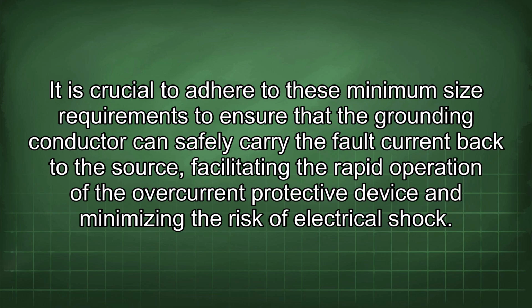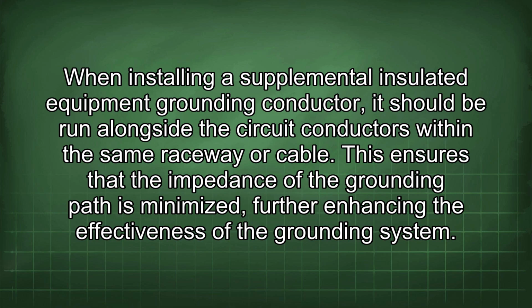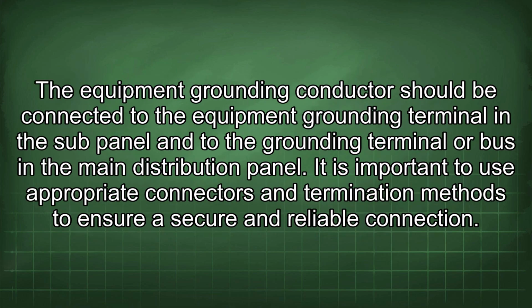electrical shock. When installing a supplemental insulated equipment grounding conductor, it should be run alongside the circuit conductors within the same raceway or cable. This ensures that the impedance of the grounding path is minimized, further enhancing the effectiveness of the grounding system. The equipment grounding conductor should be connected to the equipment grounding terminal in the sub-panel and to the grounding terminal or bus in the main distribution panel. It is important to use appropriate connectors and termination methods to ensure a secure and reliable connection.